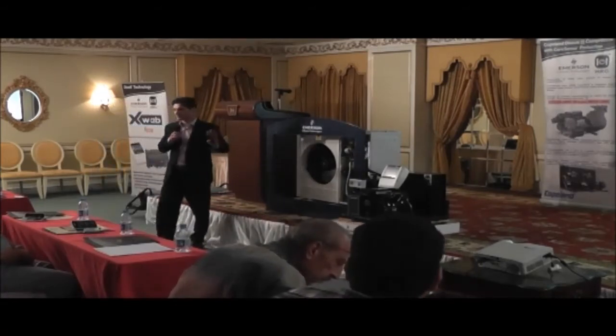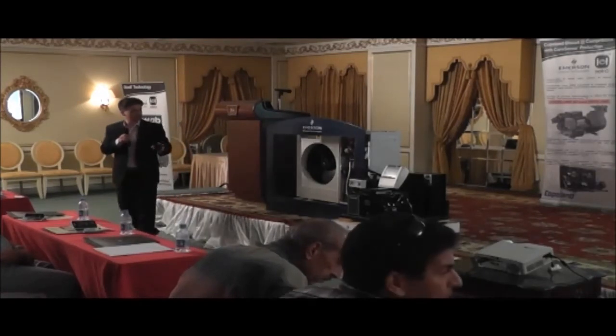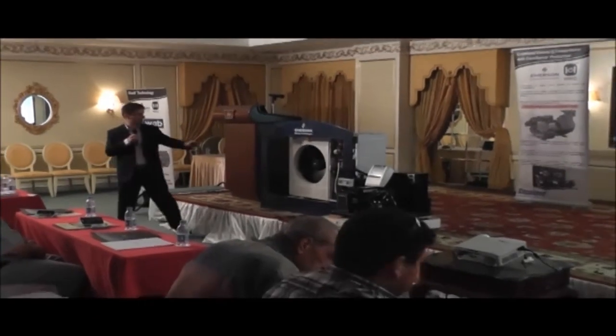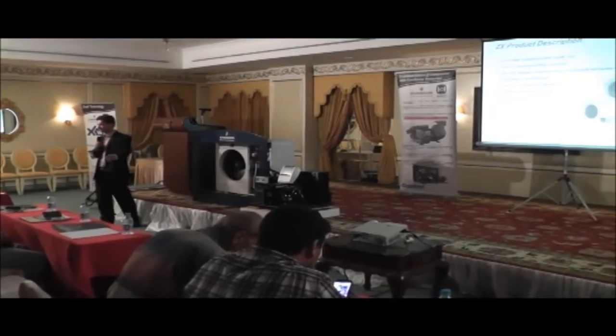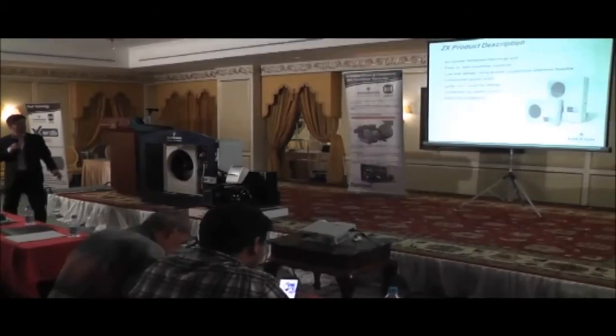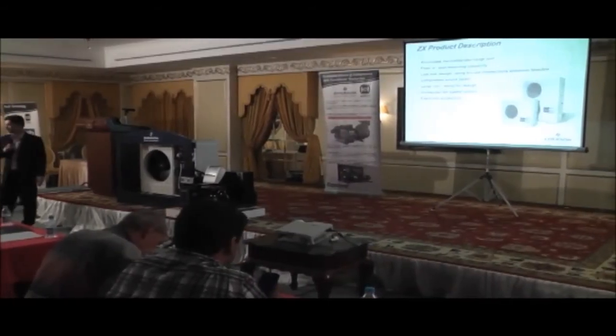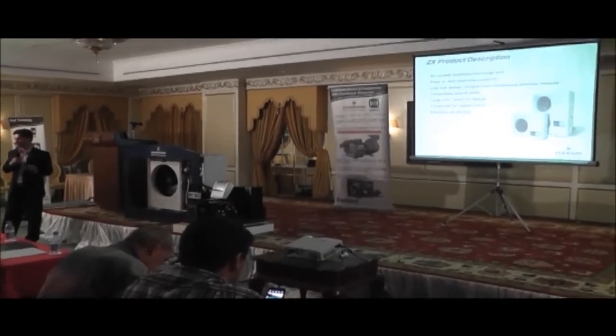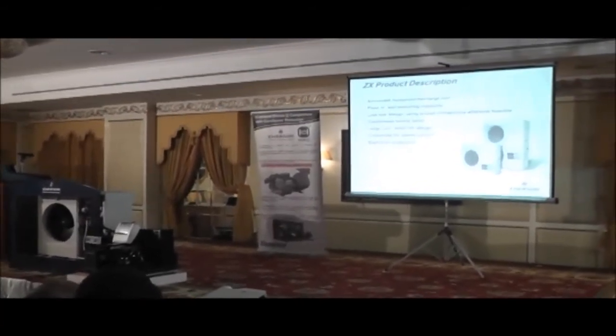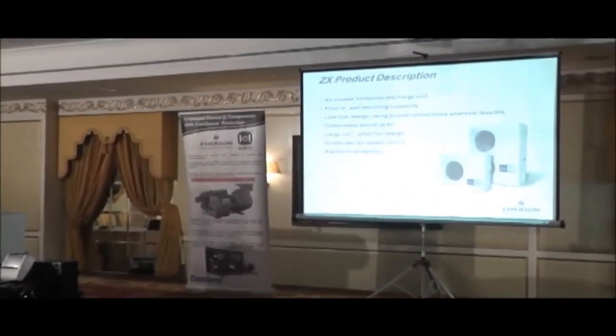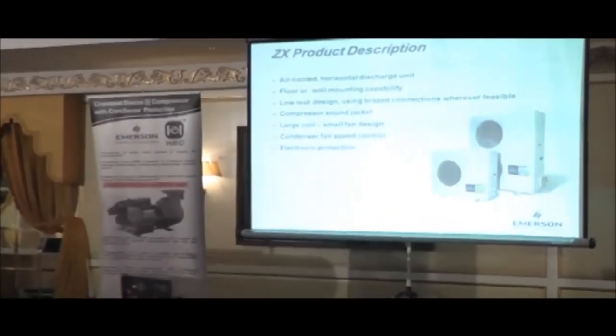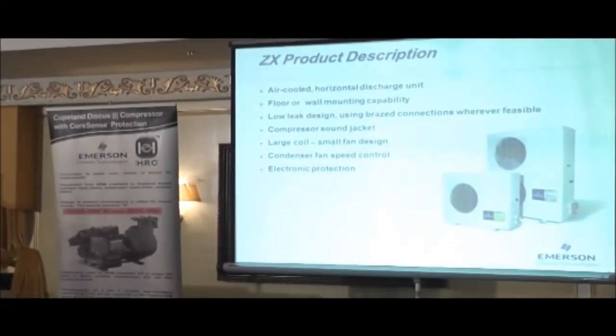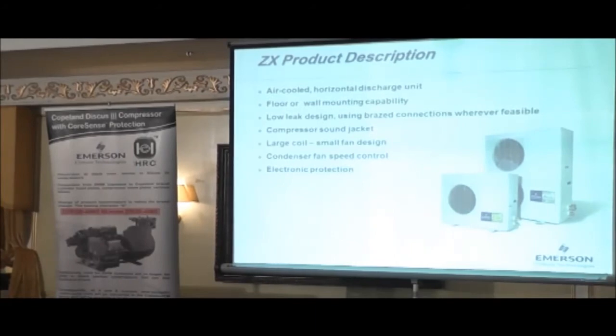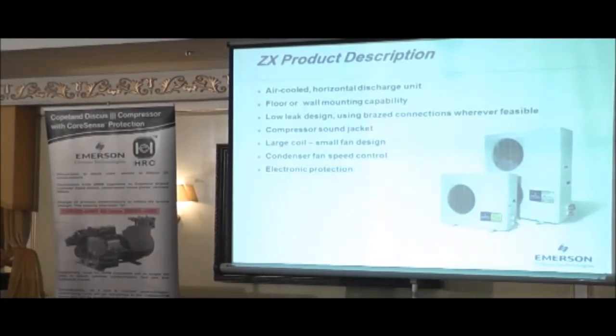If you look at the ZX product, it's an air-cooled horizontal discharge unit, so we're blowing air from the back through the fan. It can be floor or wall mounted, like an air conditioning unit, where we mount the brackets onto the side of the wall, or on the roof, or floor mounted. We've gone with the low leak design. What we mean by that is all the fittings internally are brazed connections, so we'll try and reduce leakage.